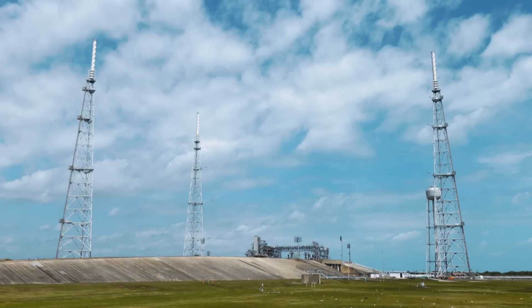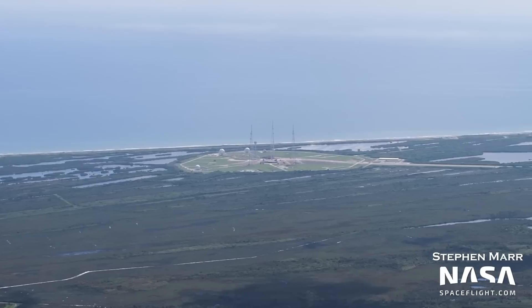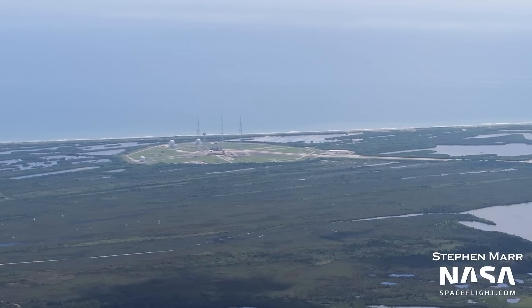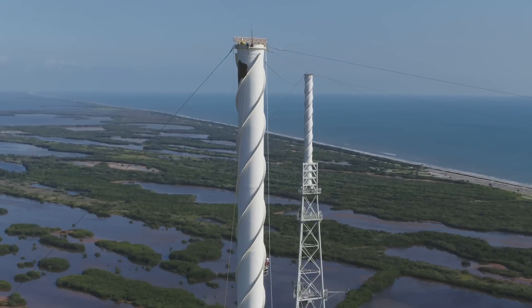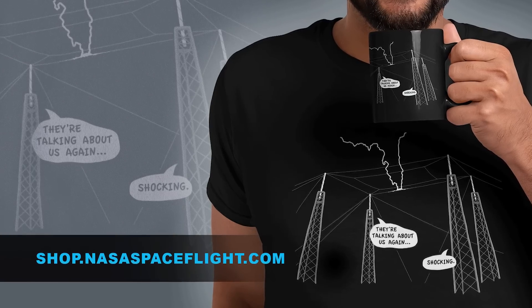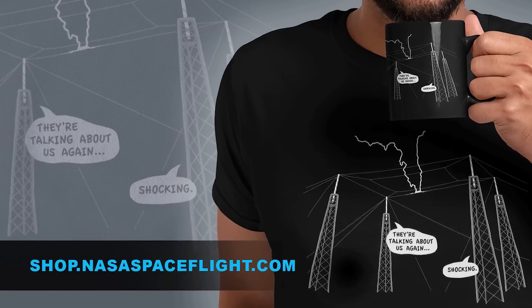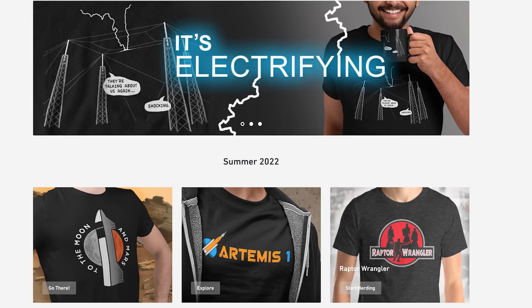The number of towers mostly comes down to the size of the area you want to protect and how the rocket flies off the pad. The new LC-39B system was originally planned to have four towers as well. But it turns out you can achieve exactly that same less-than-1% chance over 10,000 years of a bad lightning strike hitting the vehicle with three towers instead of four. So there you have it — the detailed answer to that famous question: what are those four towers? Check out our merch store for our new lightning protection theme at shop.nasaspaceflight.com. Until next time, I'm Chris Gebhardt. Later, nerds.